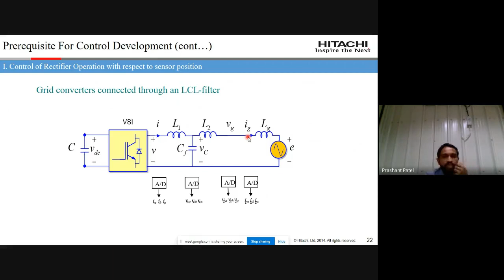If you select the current sensor at the converter side and the voltage sensor at the filter capacitor, measuring grid voltage from the filter capacitor, then this VC voltage and the current at the converter side will give you unity power factor at this point. From the phasor diagram it's clear you will not get unity power factor at VG and IG.